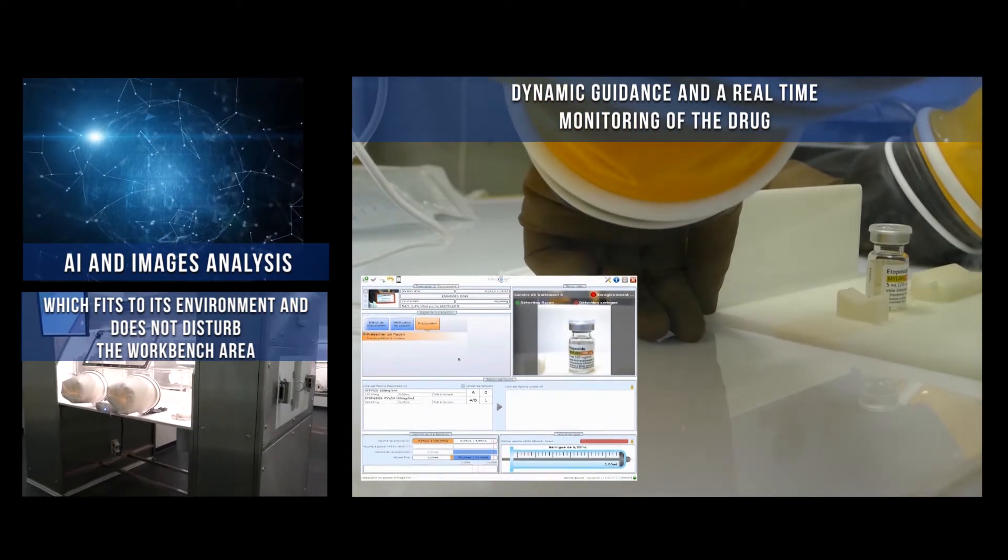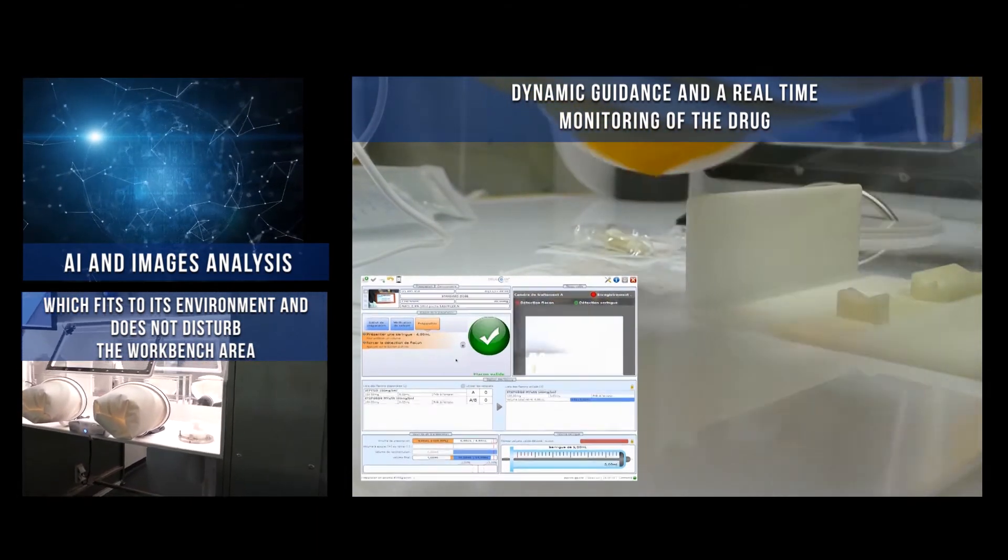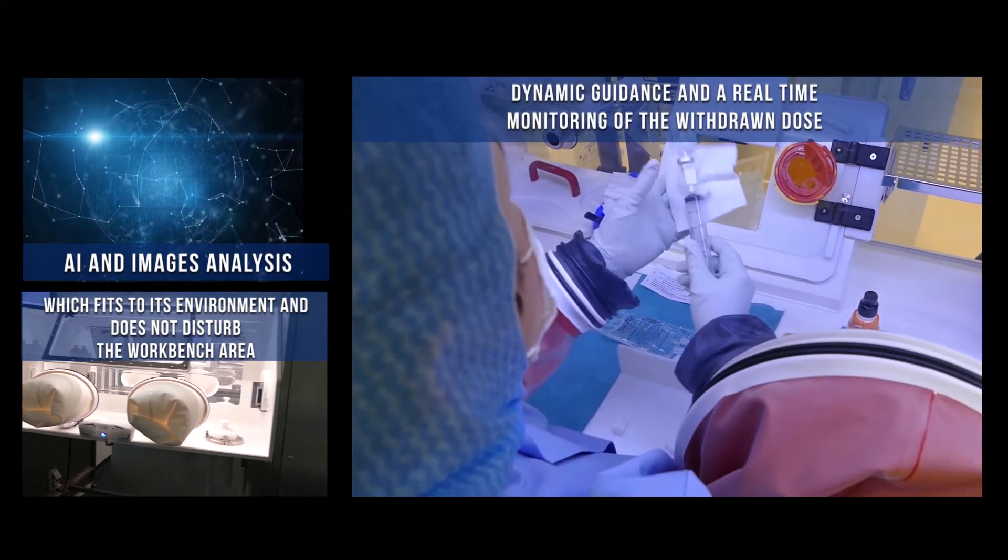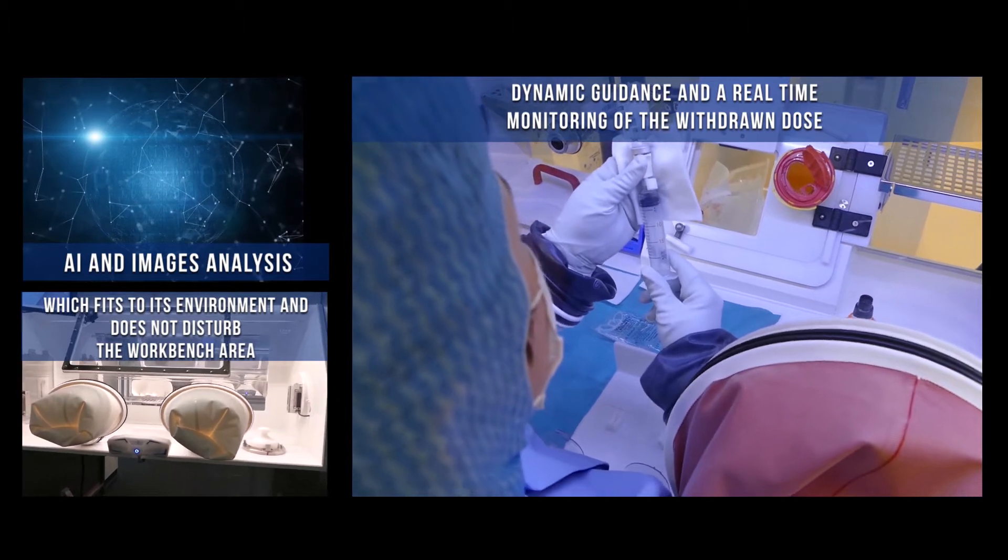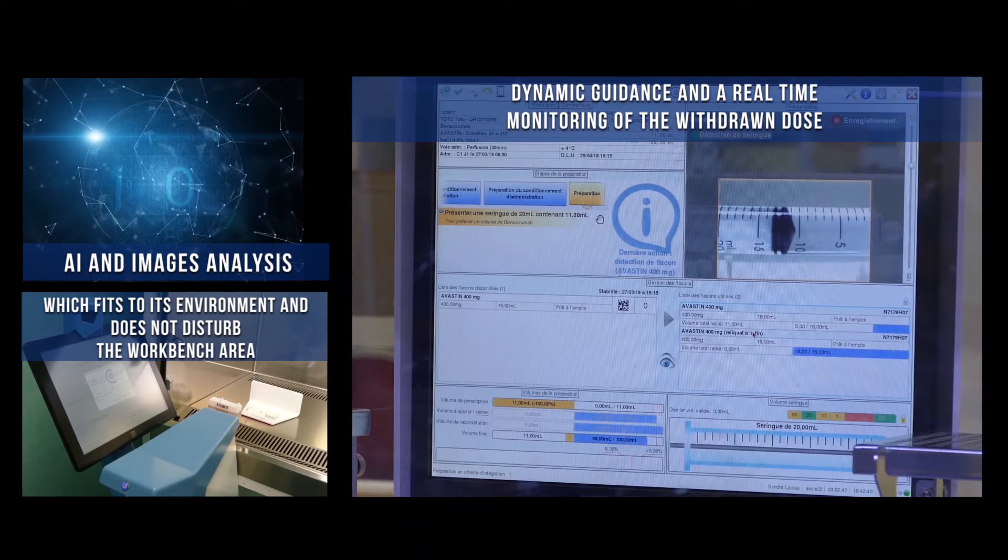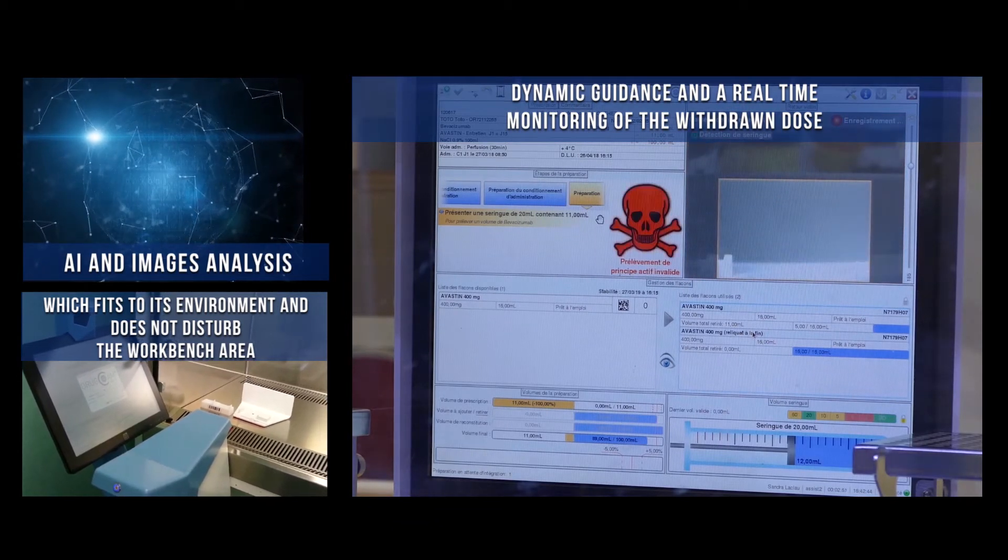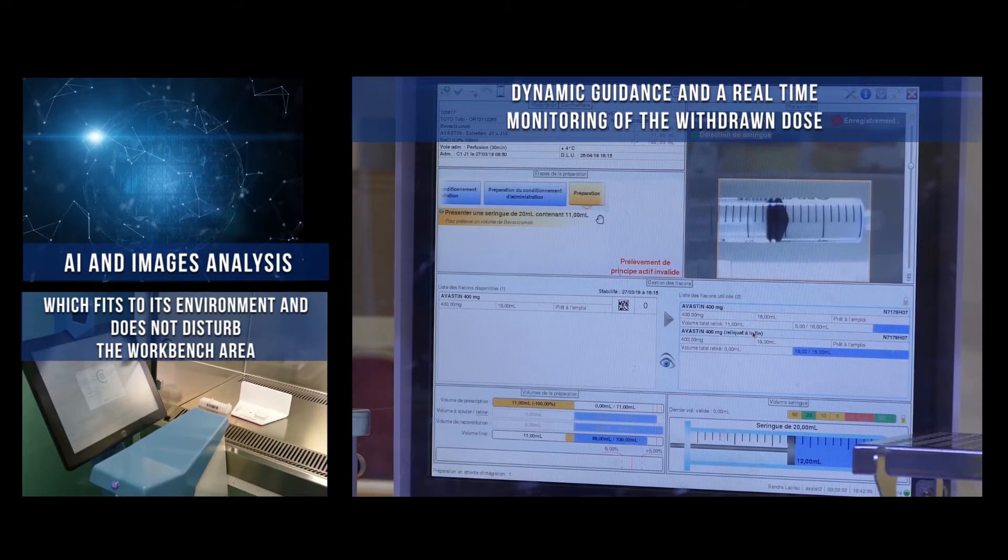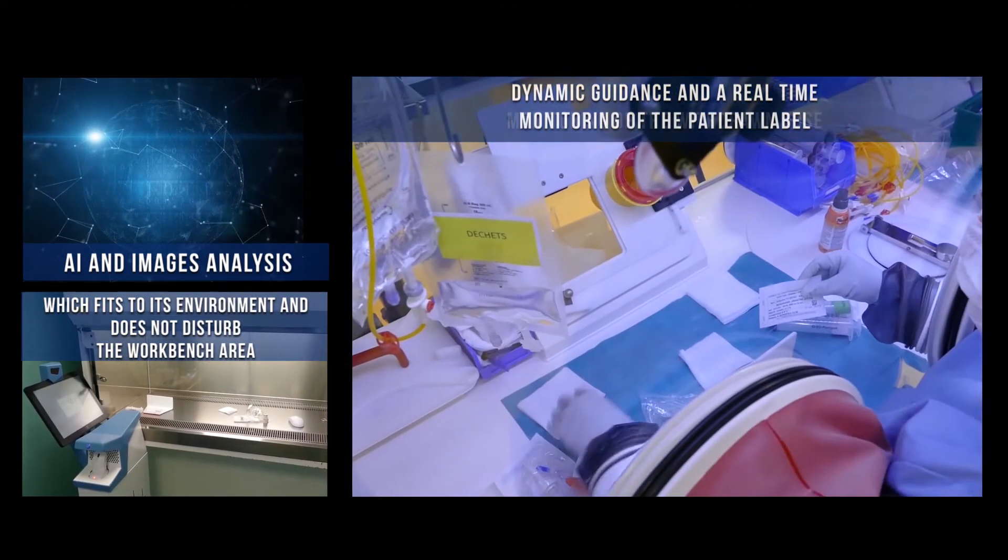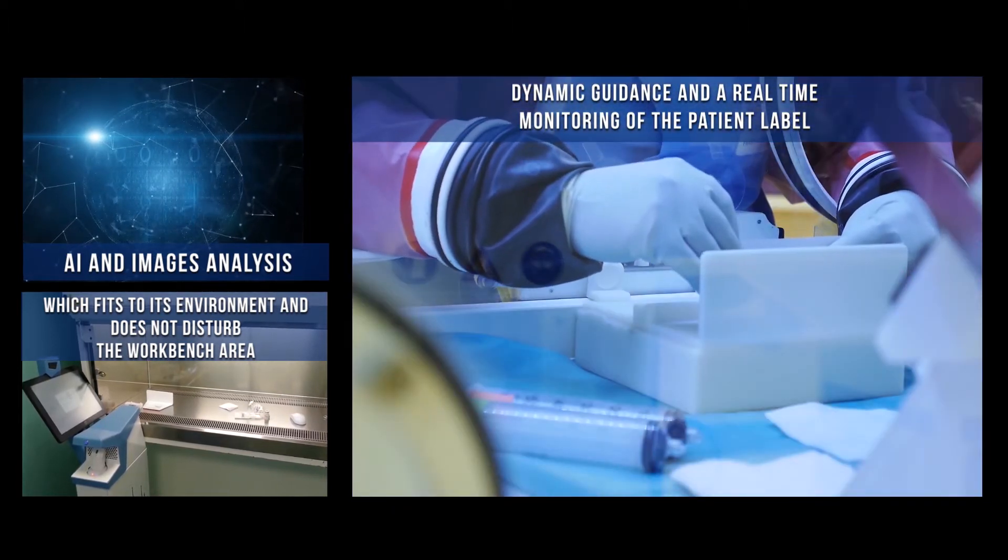As a result, the technician is now assisted by dynamic guidance and real-time monitoring of the drug with or without data matrix, but also by real-time monitoring of the withdrawn dose and by real-time monitoring of the administration vehicle labeling.